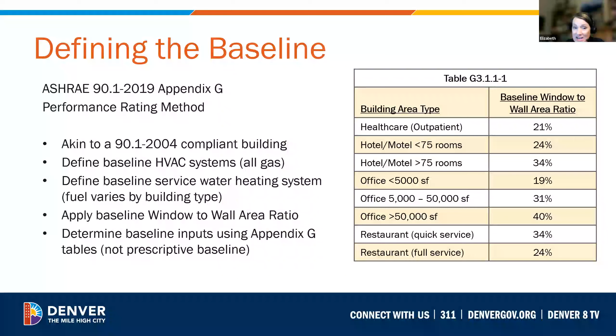Energy modelers will then select the HVAC baseline by following these rules, which might be a little different from what we are used to. The primary baseline is determined by the building type with the largest floor area first. Then you select the baseline by the end use, number of floors, and gross conditioned floor area.